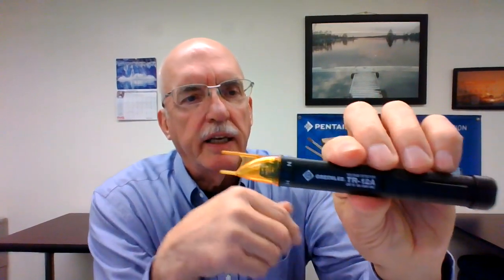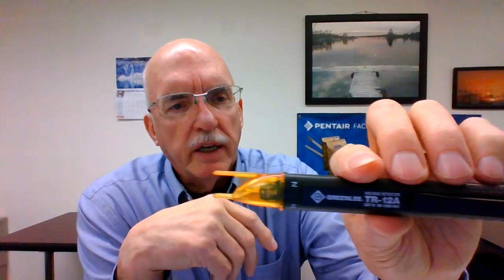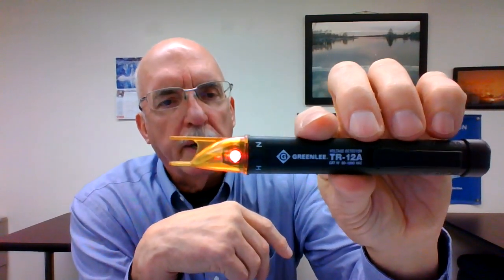Not a bad price. This model here is a Greenlee special. It's a new device that's made for you electricians and electrical inspectors to test the tamper-resistant receptacles. Because as you know, a tamper-resistant receptacle, which I'm going to be covering in an upcoming issue of this vlog, you need to put a prong in each slot for anything to enter. So this here has a hot and a neutral. If you put it in backwards, it will give you a signal saying that the polarities are reversed on the receptacle itself.